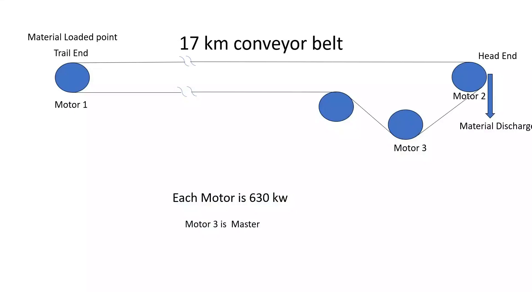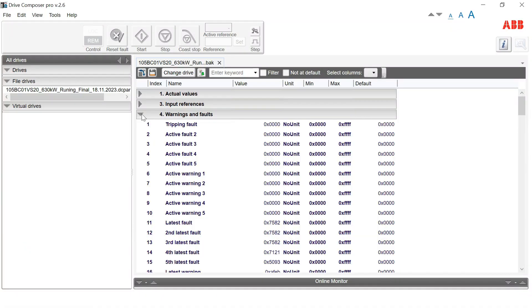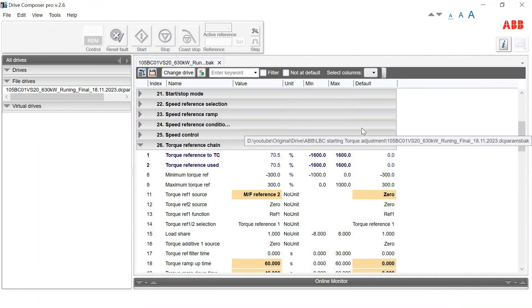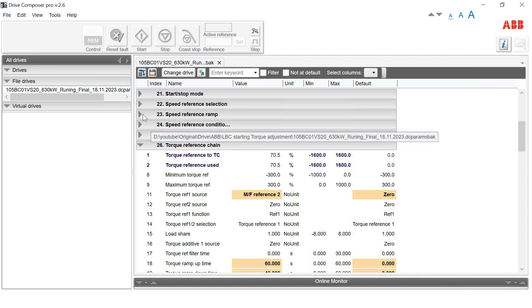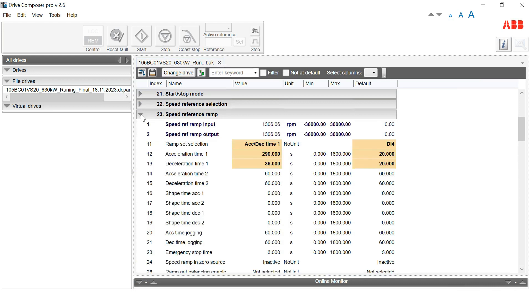So we checked the parameters and made a change. Looking at the trend again, VS20 is not ramping up its torque — it is taking the torque very slowly. So you need to increase the ramp, which means decreasing the acceleration time. There are two types of acceleration: one is speed acceleration and the second is torque acceleration. You can see the speed acceleration here is set to 290 seconds — it is a long conveyor belt, so speed should increase slowly.